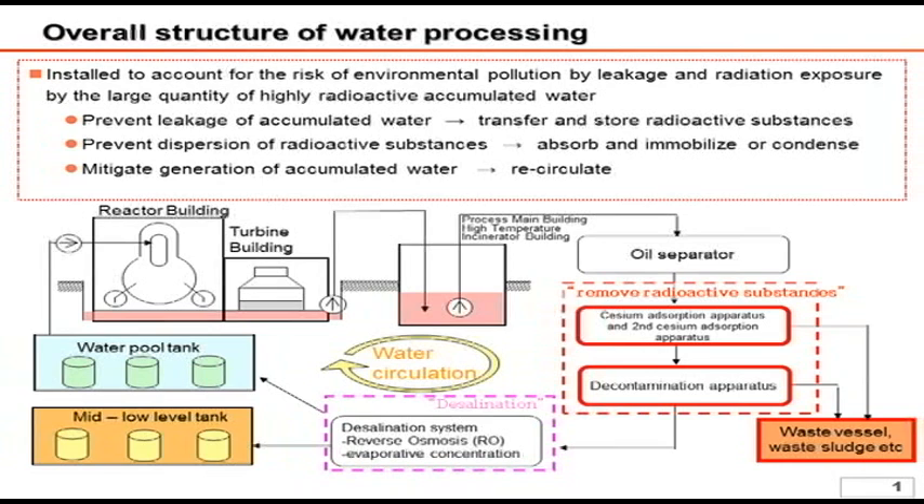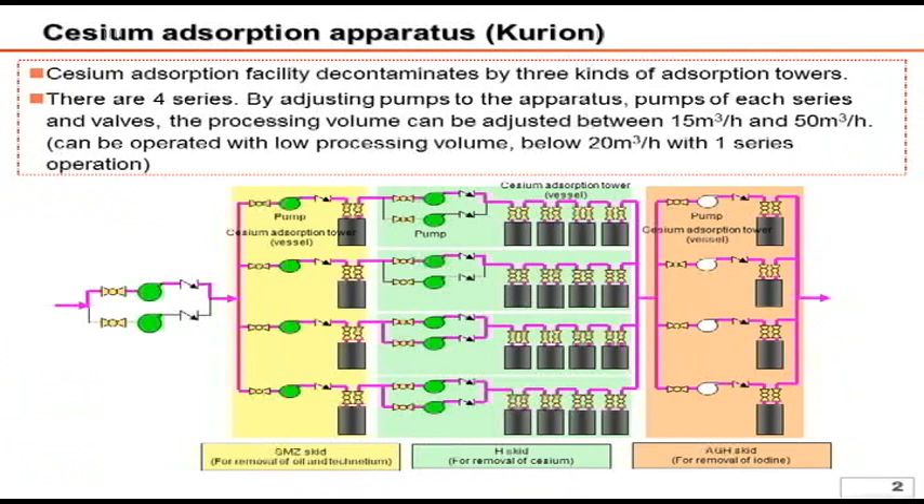Such a role is served by two facilities: the cesium adsorption apparatus and decontamination instruments. First, Kurion's Cesium Adsorption Apparatus. We have installed four series of the system, and currently two series are under operation. The total process capacity is 50 cubic meters per hour, and each series can process between around 10 to 20 cubic meters per hour.